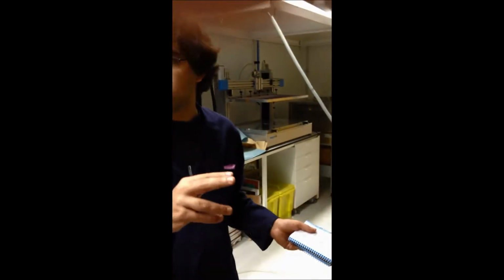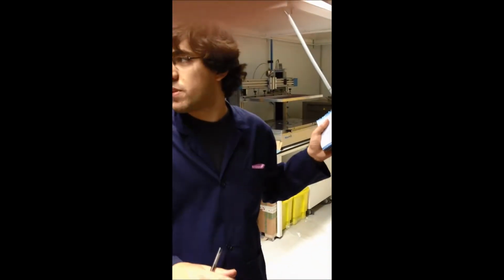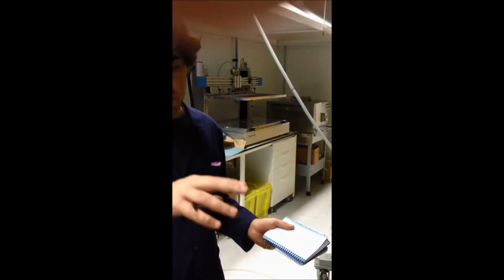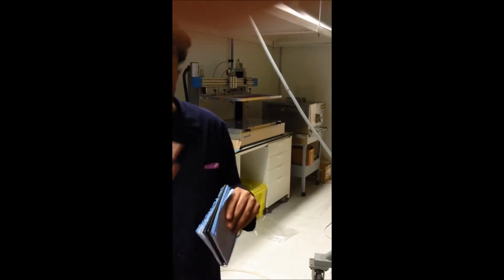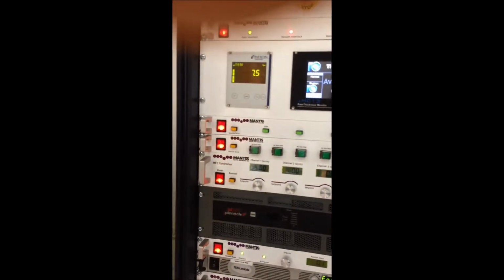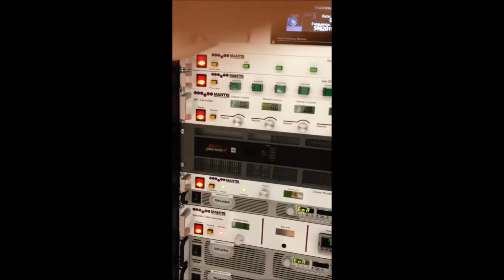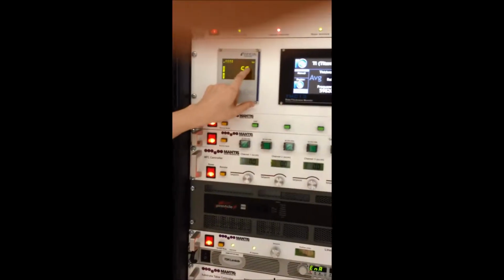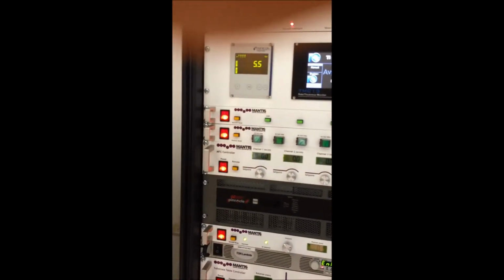The switches between vacuum pump and turbo pump, will they switch automatically at a certain vacuum pressure? No, you need to do it yourself, unless you write a procedure for it. You can always write a pump-down procedure. So now we are waiting for the pressure to lower to a point where we can use the turbo. When you see -1, then you can turn on the turbo.